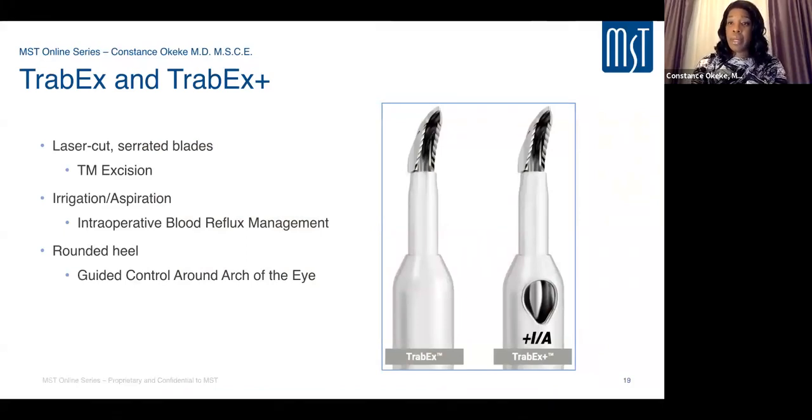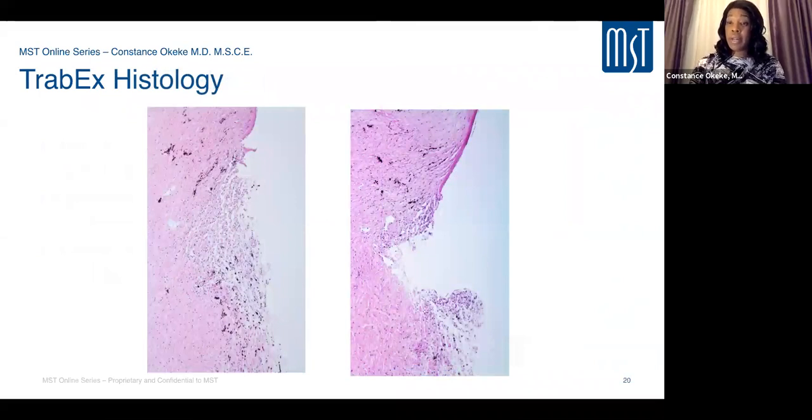TrabEx and TrabEx+ differ from Trabectome in that they are single-unit devices rather than a whole fluidic system. There is no electroablation — instead, laser-cut serrated blades excise the trabecular meshwork tissue. The blade width ensures a wide enough central band is removed to separate the leaflets, minimizing scarring and closure of collector channels. TrabEx+ adds irrigation and aspiration from compatible phaco machine units.